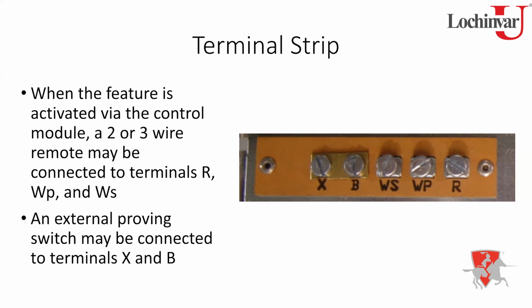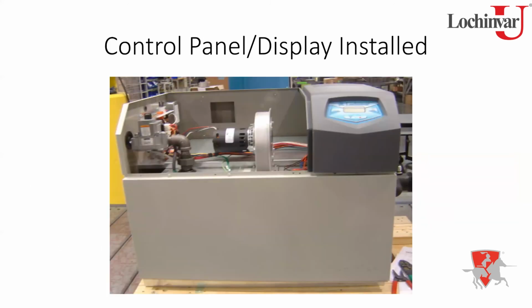So now we've got our control panel on, we've got everything wired up, it's ready to go. So the last step on the line will be, they'll actually hook it up. They're going to run power to it, they're going to run gas, they're going to run water, they're actually going to fire the unit up, and they're going to do the settings, right? So the manifold pressure is going to be set, the air pressure is going to be set, everything's going to be fire tested here at the factory, and it's going to be good to go.